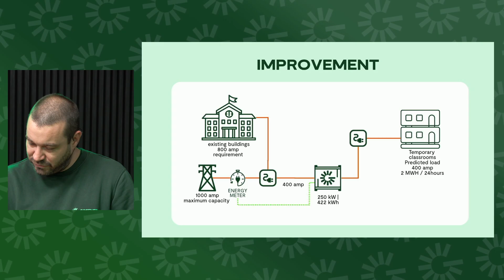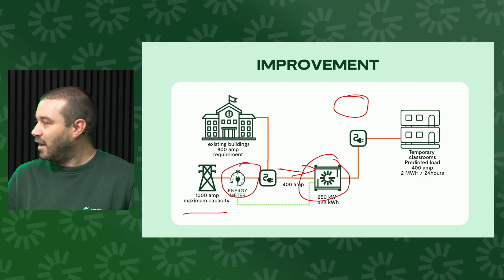And that would have involved going into a grid following situation with an energy meter, because that would have meant that we could have taken a full 400 amps worth of cabling from that grid connection, measured it, and then allowed the battery to adjust its set point either side of 400 amps, which in this case would have meant that the generator that was sitting up here was no longer needed. And we could have scaled up easily in the wintertime. Added an extra battery. More capacity needed. Yeah. And scaled down again when the capacity was not necessary.